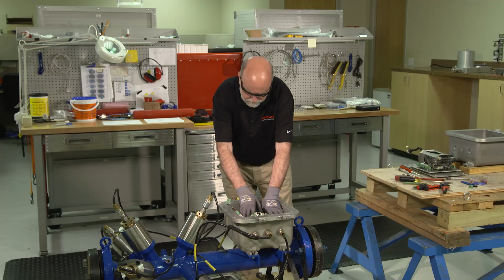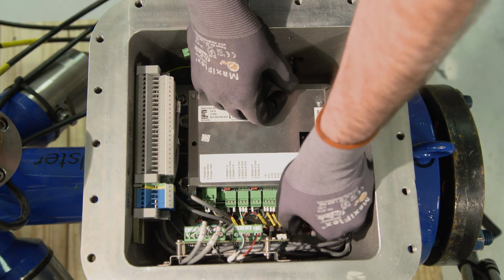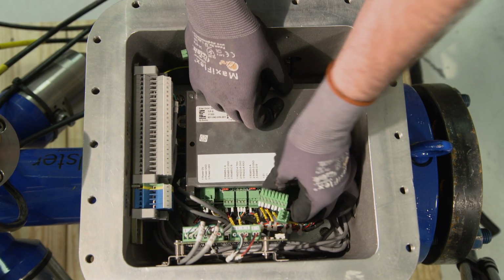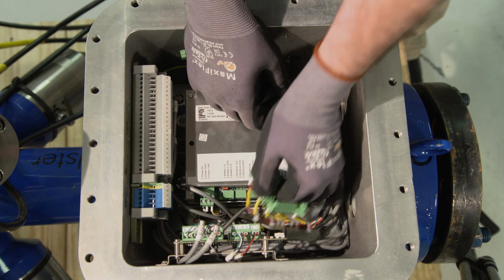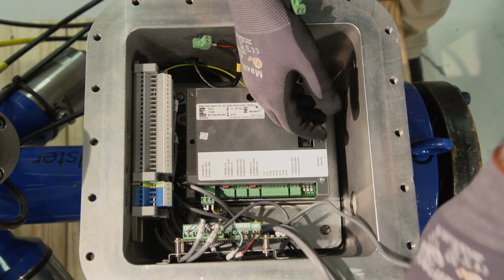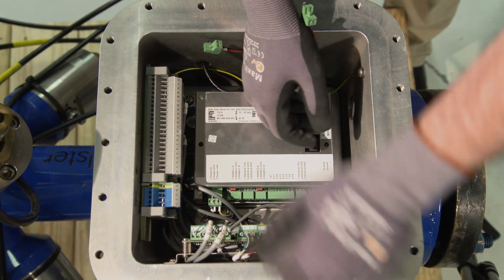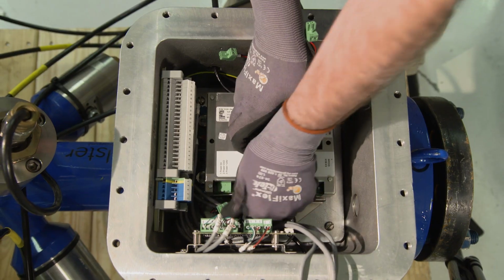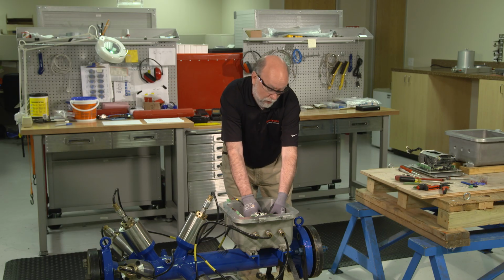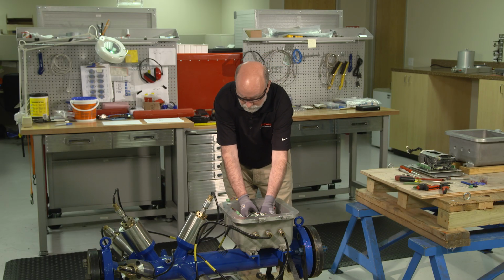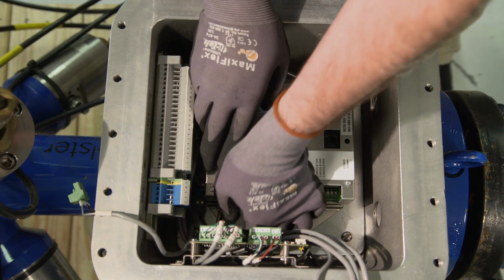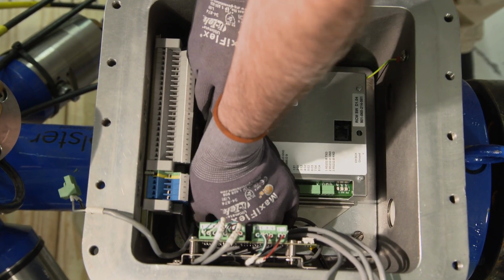I think I touched on this, but just to reiterate, before we start working on the meter, you need to make your gas control or measurement people aware of the fact that you're going to be without measurement on this device for a period of probably 1 to 2 hours. Disconnect the transducer cables. All these things plug in.